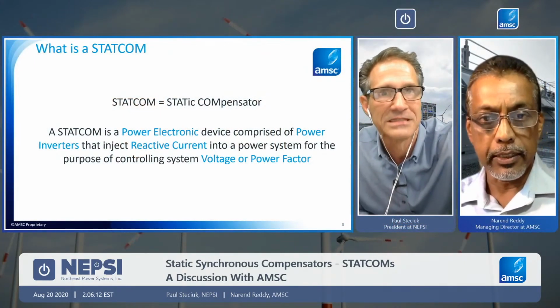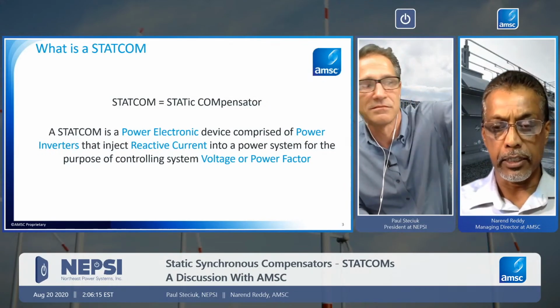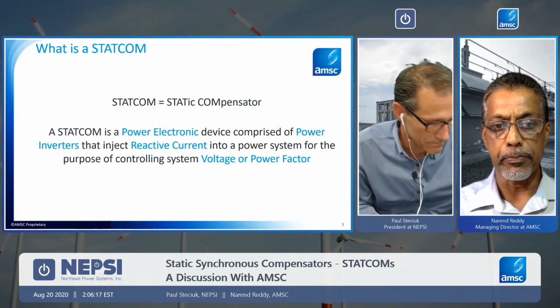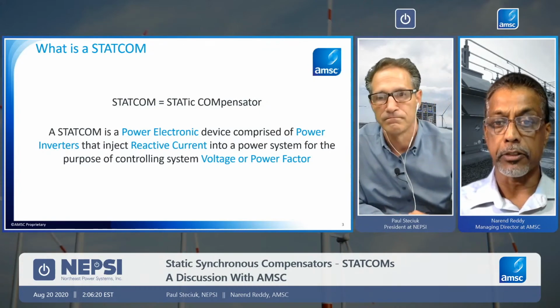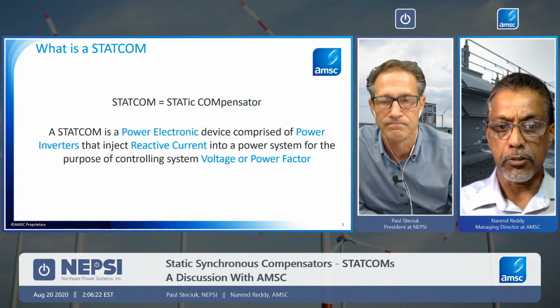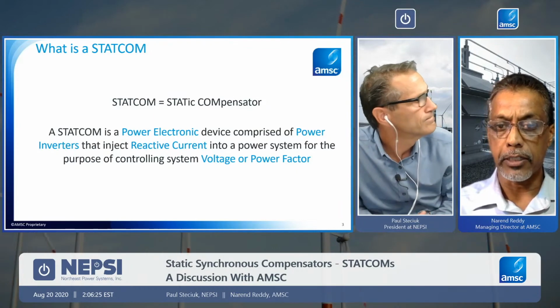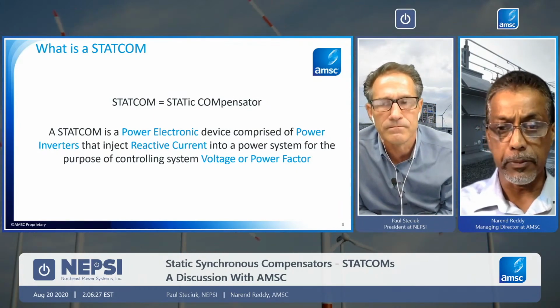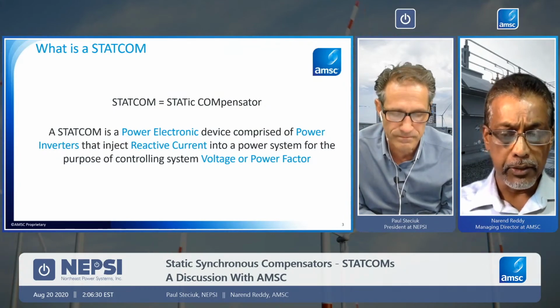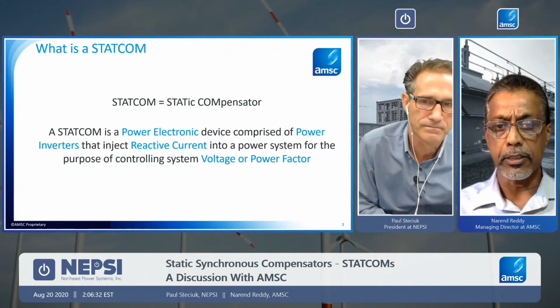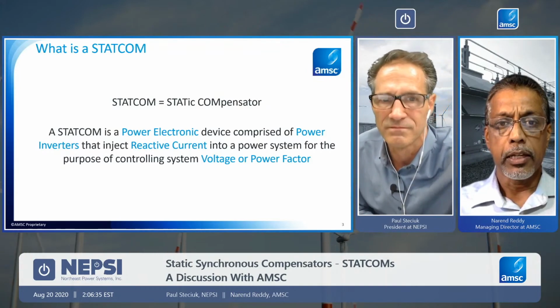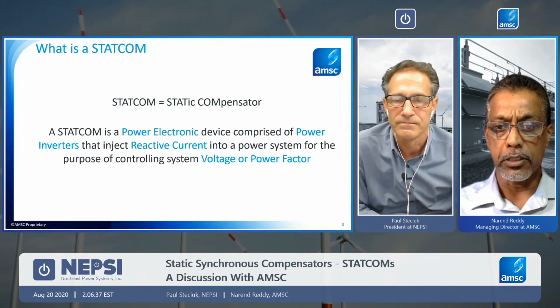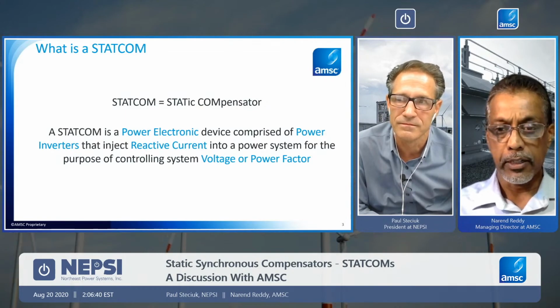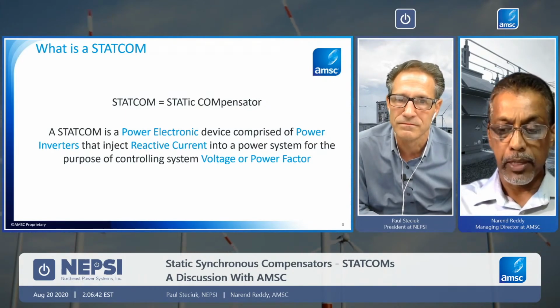Sure. Let's start on some basics of what a STATCOM is and what it does. So what is a STATCOM? STATCOM is a short form name for static compensator. A static compensator is a power electronic-based device comprised of power inverters that inject reactive current into the AC power system. And when you are able to inject reactive current, capacitive or inductive, you have the ability to influence the system voltage or the power factor of the system at that connection point.